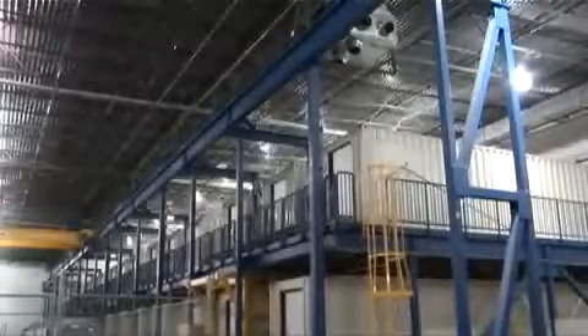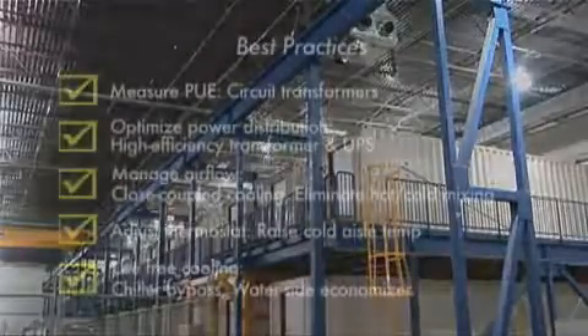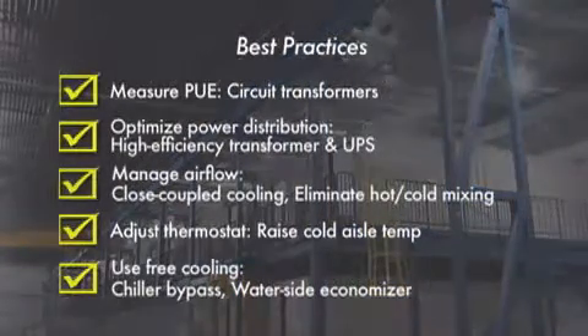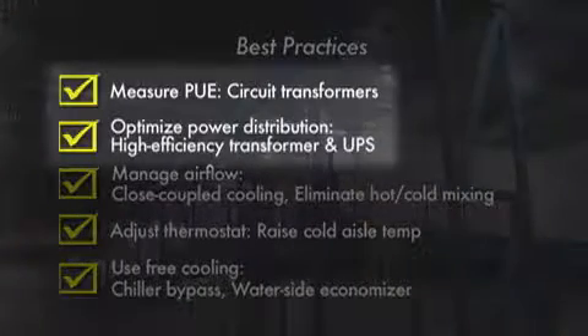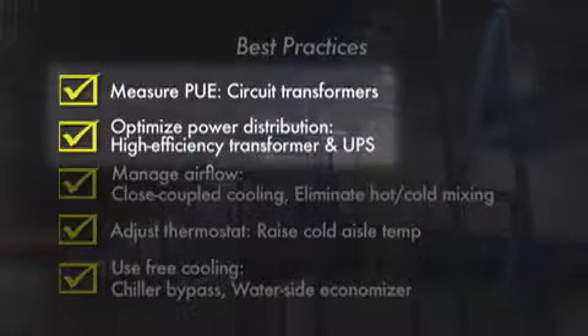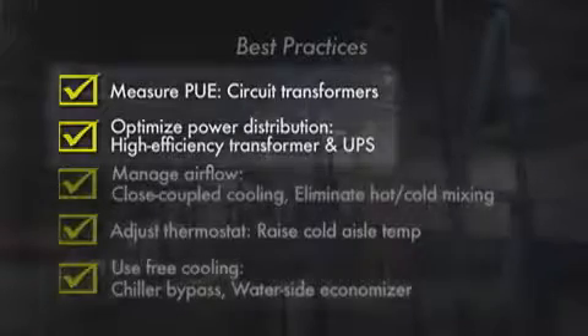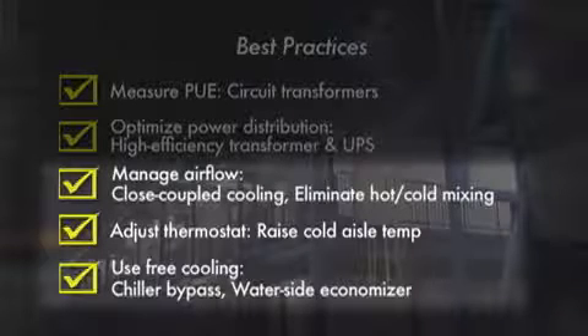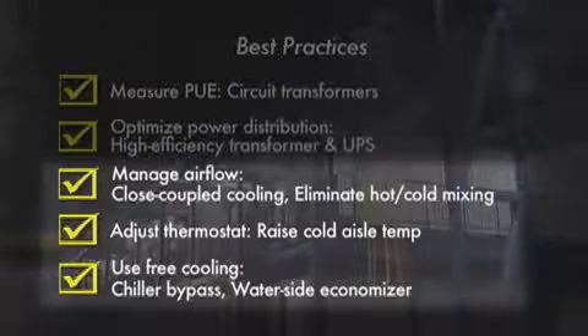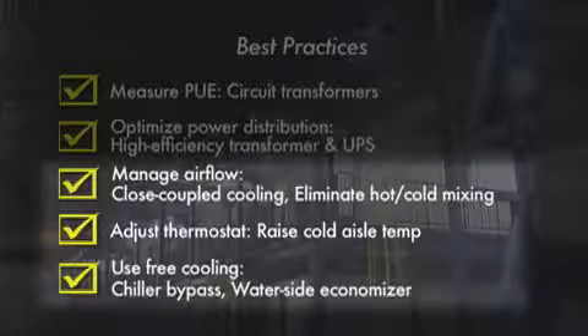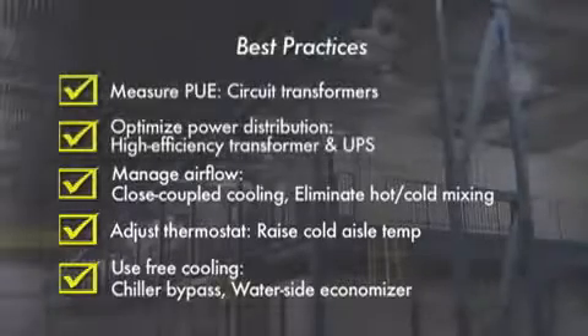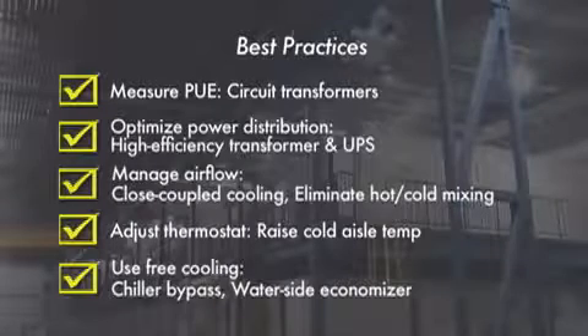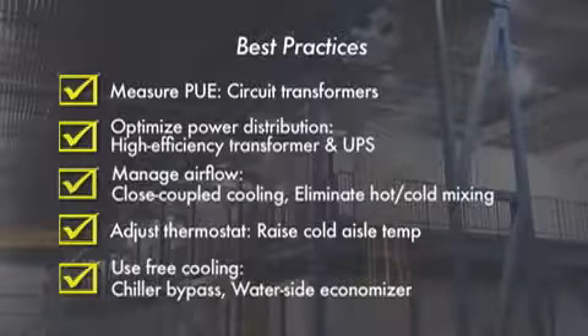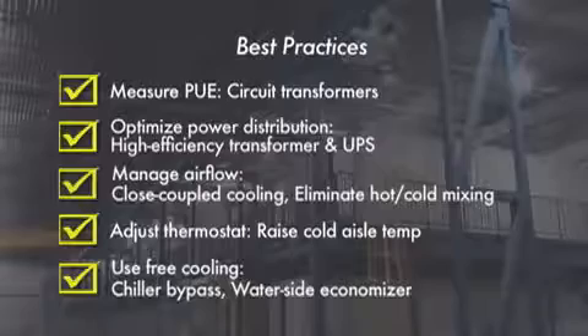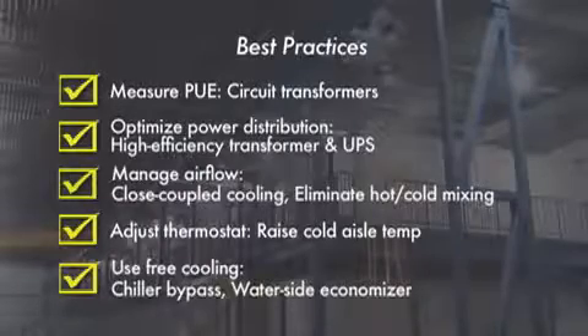We end our video tour with another view of the hangar and a summary of the best practices incorporated into this data center. Recapping, on the electrical side, we saw the use of high-efficiency transformers and UPSs, along with the necessary circuit transformers for accurate PUE measurements. On the cooling side, we touched on many aspects designed to allow raising of the temperature inside the data center and the associated reduction in chiller usage hours. One last thing to note, the best practices we presented here are the main reason we've been able to achieve our PUE results and can be implemented in most data centers today. Thanks for watching.